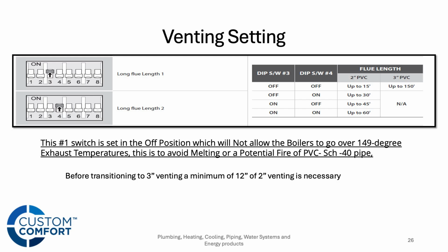We're kind of saying the quiet part out loud here. On the vent material, these are approved for use of PVC venting, as well as stainless steel, polypro, Centrotherm, or CPVC, like a 636 type of venting. But out of the box, dip switch number 1 of that boiler is going to be set to the off position. It's not going to allow the boiler to fire exhaust gas temperatures of over 149 degrees, right? That's to prevent melting of PVC, what it's rated for. So if we're going to use a proper boiler vent material, we can make that dip switch adjustment and go above that, where we're not worried about melting a polypro, Centrotherm, stainless steel type of venting material.